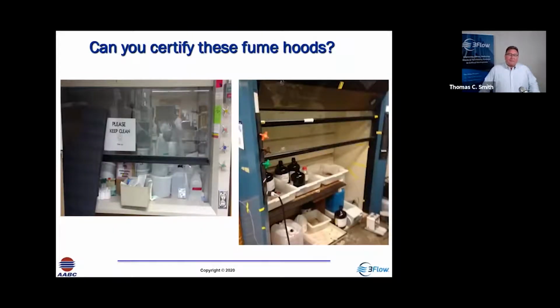Another problem: can we certify these hoods? If you look at this hood on the left, it says, please keep clean. But it's so cluttered with materials, how would you possibly test it? Yet there's a sticker on the hood. And over here, you can't close the sashes. There's stuff protruding out of the front of the sash. Again, we would be reluctant to do any type of testing on these hoods because they're just not being used appropriately. So the answer to this question is no. You should not certify these hoods, because then you would be verifying that they operate correctly, and that's not the intent of the test.